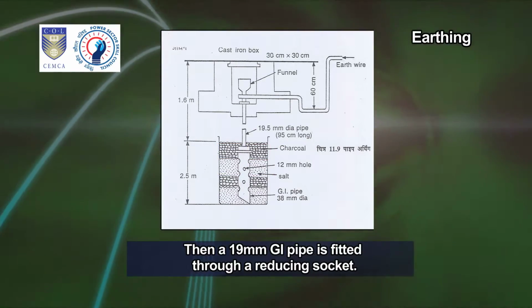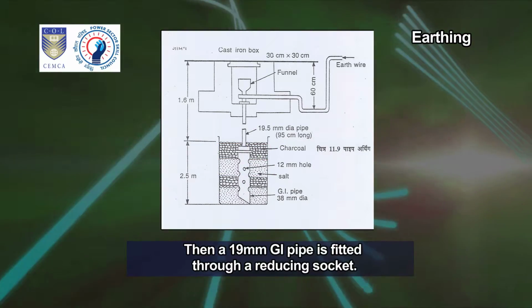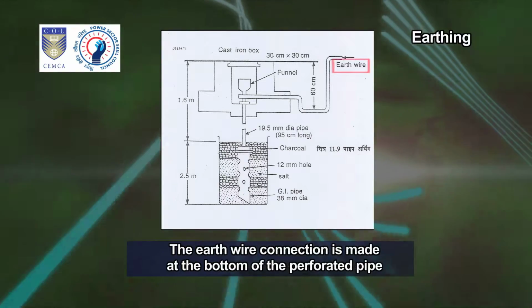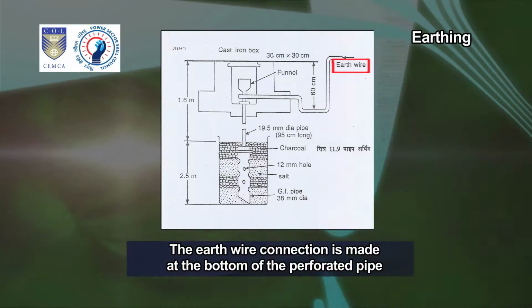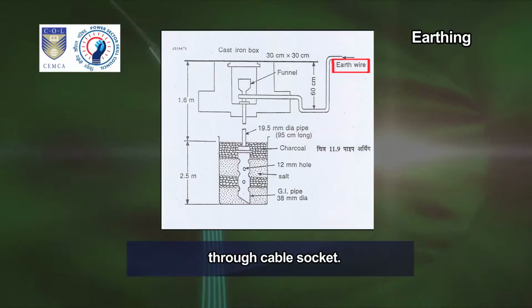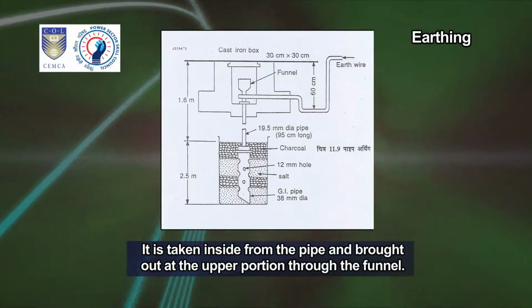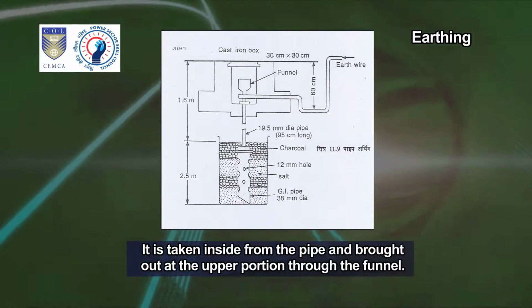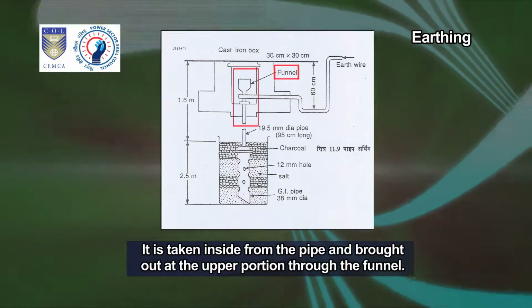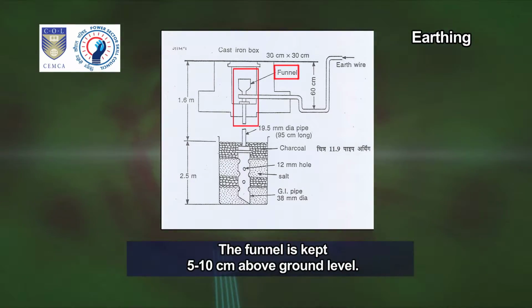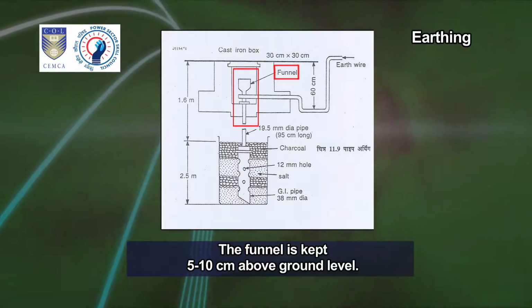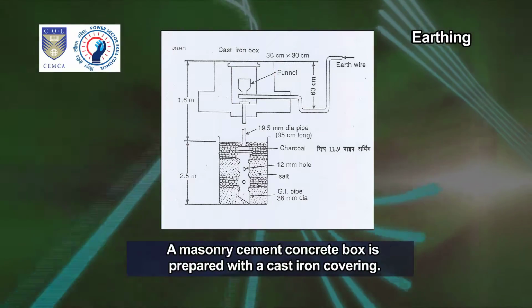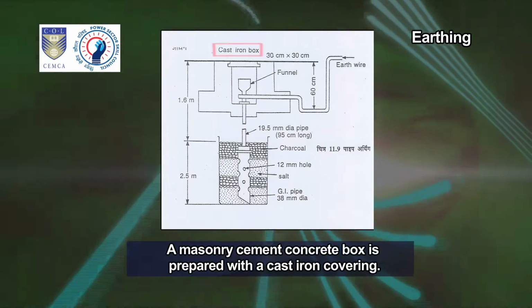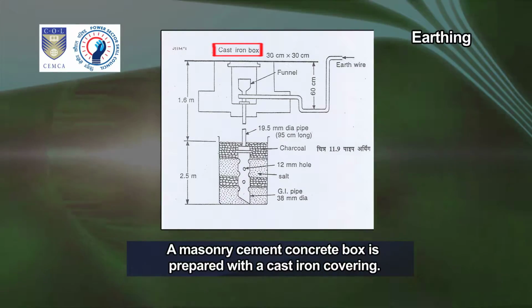Then a 19 mm GI pipe is fitted through a reducing socket. The earth wire connection is made at the bottom of the perforated pipe through a cable socket. It is taken inside the pipe and brought out at the upper portion through the funnel. The funnel is kept 5 to 10 centimeters above ground level. A masonry cement concrete box is prepared with a cast iron covering.